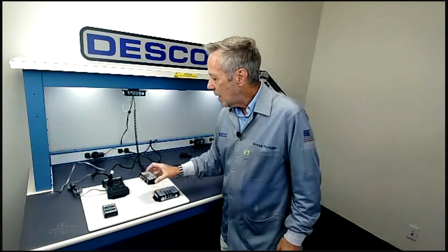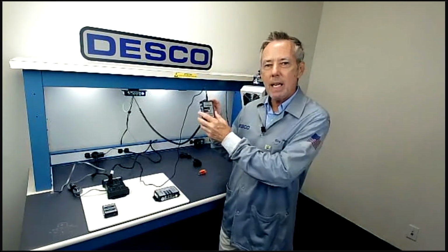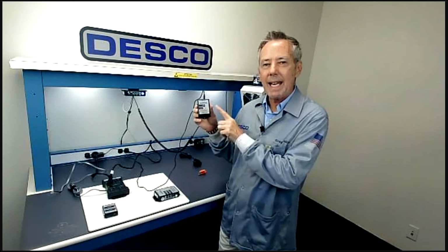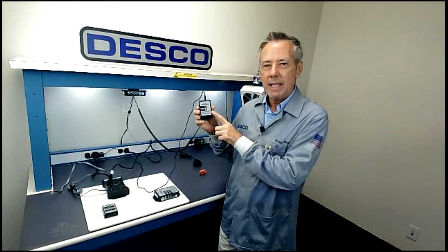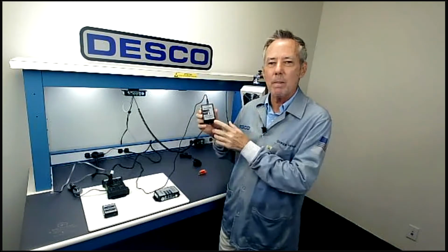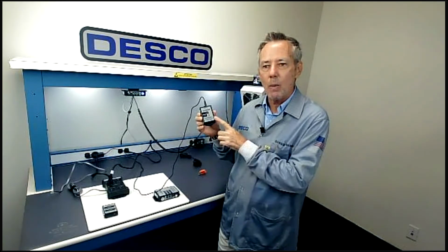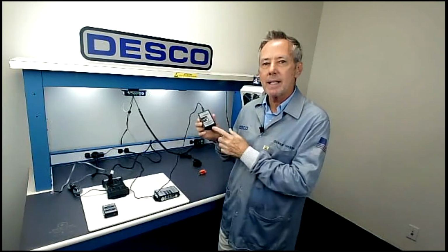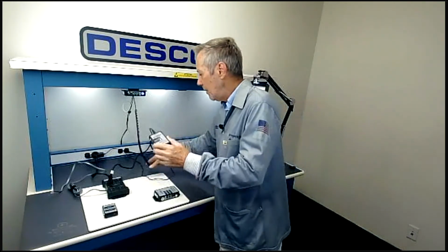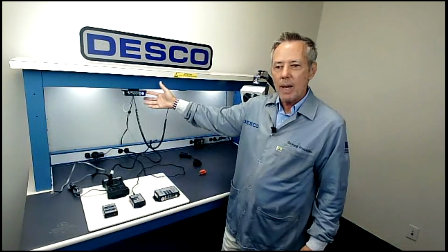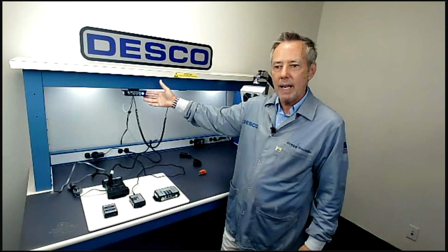Now let's talk about the speed. This monitor right here and our mini monitor will alarm or react in less than 50 milliseconds. That's one of the fastest monitors, if not the fastest monitor on the market. Certainly the fastest single wire monitor. So if you have a break in your connection, you're basically getting an instantaneous alarm. The FullTime monitor is less than 100 milliseconds, so it's extremely fast also, all right?